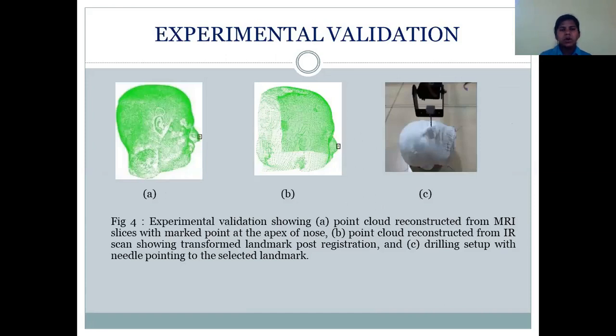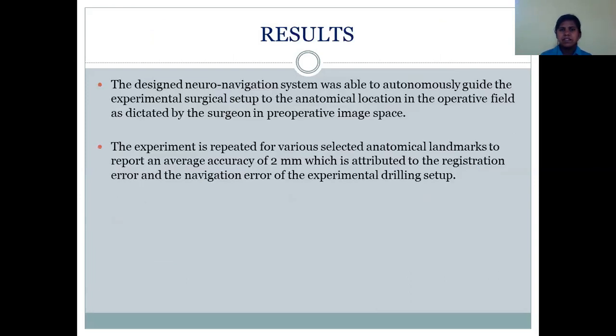This is the experimental validation. The doctor was allowed to make an annotation on the 3D point cloud reconstructed from the MRI images. This point is then transferred to the IR-scanned 3D point cloud on the surgical table. The experimental setup was able to navigate and point to the annotated location perfectly in the surgical scene. The neuronavigation system successfully guided the experimental surgical setup to the anatomical location in the operative field as dictated by the surgeon in the pre-operative image space. The experiment was repeated for various anatomical landmarks, reporting an average accuracy of 2mm, attributed to registration error and navigation error of the experimental drilling setup.